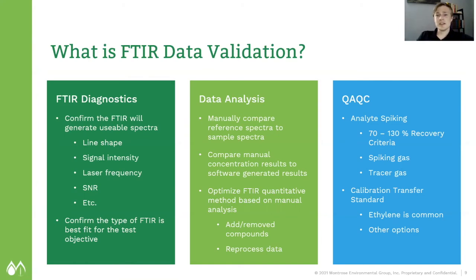In terms of QA/QC, analyte spiking is arguably one of the most important pieces of criteria that we do in the FTIR world. We're taking a very small slipstream of calibration gas, introducing it into the sample, and we're hopefully getting a good recovery. So usually we're looking at about a dilution factor of 10% or less. And we're spiking ppm, sometimes ppb into a stack, and we're hopefully getting a good recovery. It's a really, really good, powerful piece of QA/QC to not only ensure that your sampling systems are working correctly, but that your methods and recipes are good.